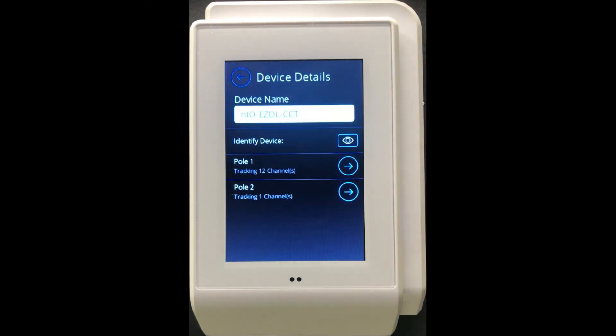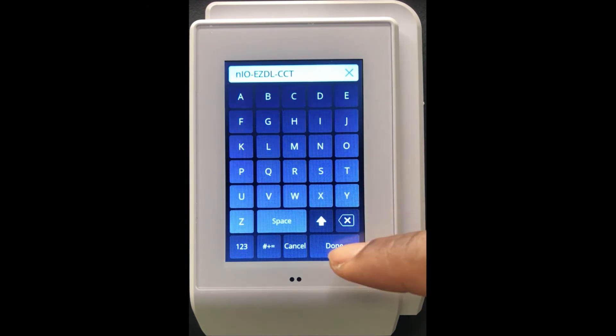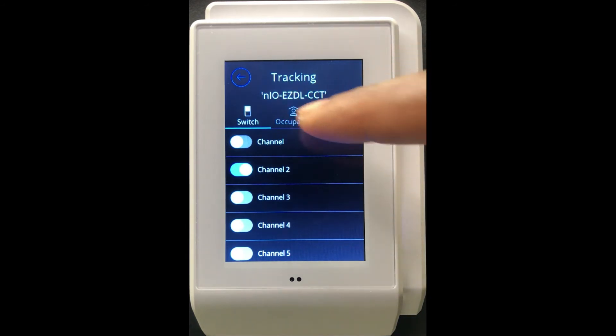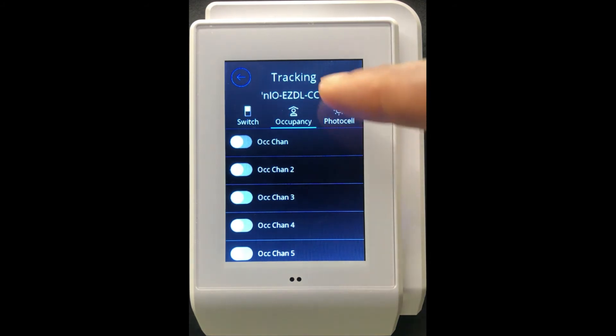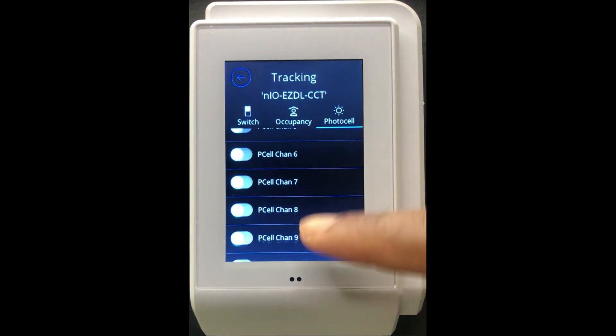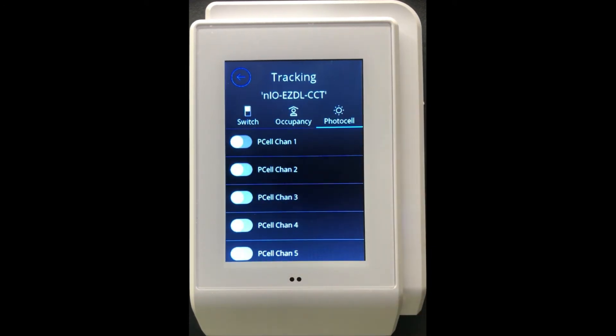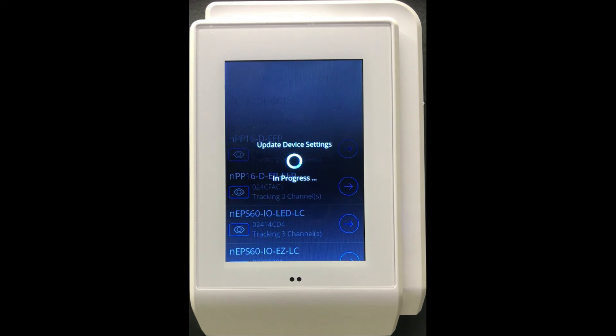When done, I can come back, and if I want to rename the device I can tap back here and associate any name I'd like — the maximum word length is 20 characters. Coming back again, the CCT pole right now is only tracking channel 2, but I can modify it to track any other channels. One key thing to note is that the CCT pole does not have the ability to track occupancy channels nor photocell channels. That's why, if you scroll across, you'll see that neither occupancy nor photocell channels have been associated with pole two of this Neo CCT.